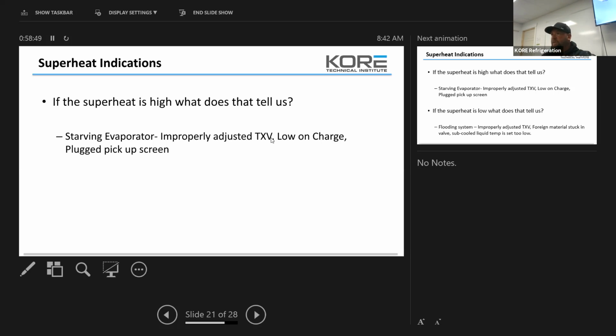Once you make that adjustment, you need to give it 4 to 5 minutes. The second thing is we never go after a TXV until we're close to optimal operating temperature, within 5 degrees. After you've done everything and cleared any plugged screen or restriction, and you know it's feeding and you can hear it trying to throttle, but you're still not getting good superheat, and you get that case down close to temp but it's not quite where you want it, or it's not recovering fast enough, then you get on that TXV.